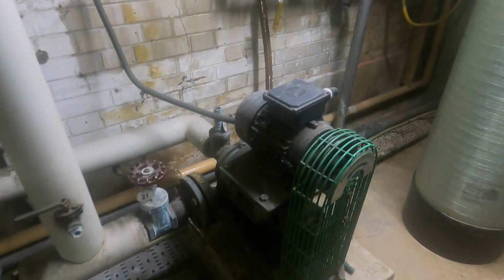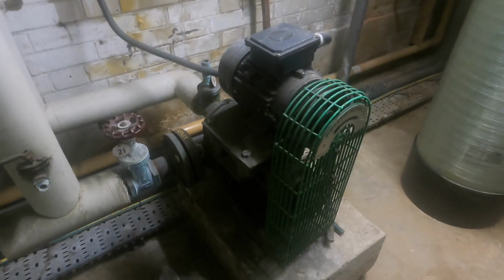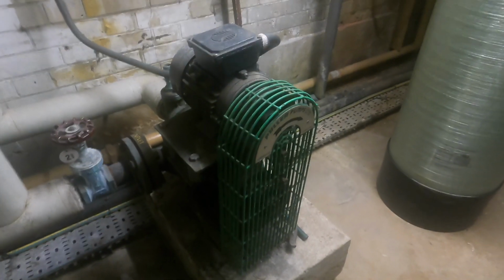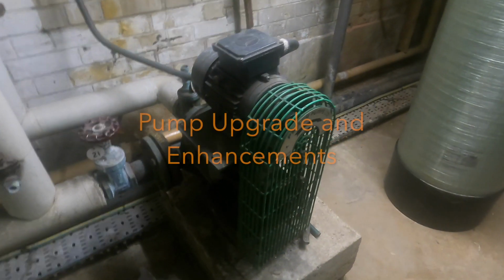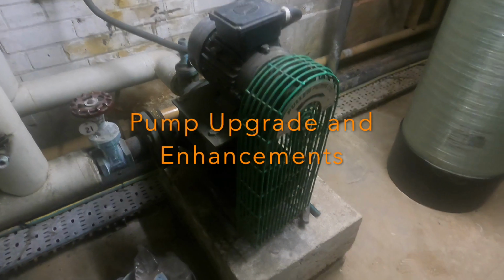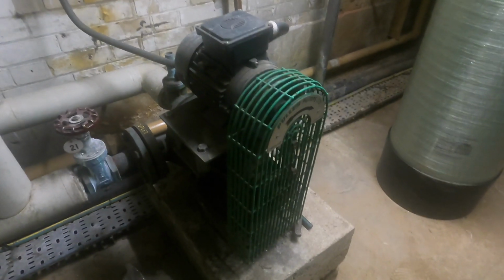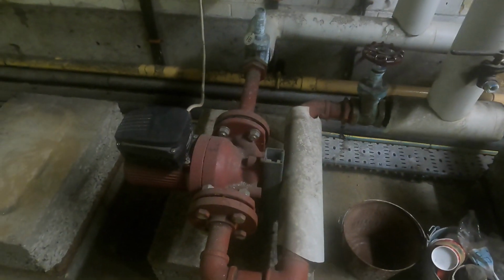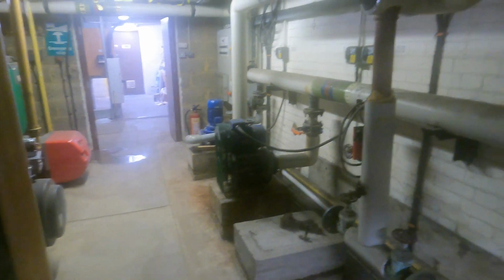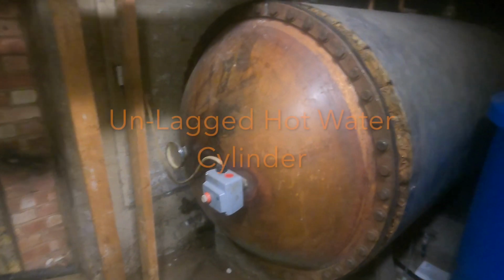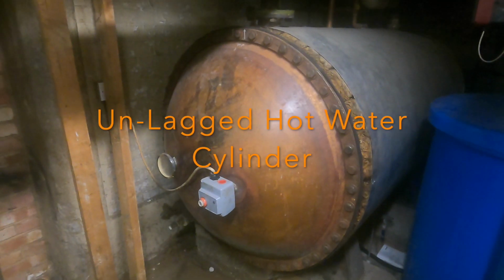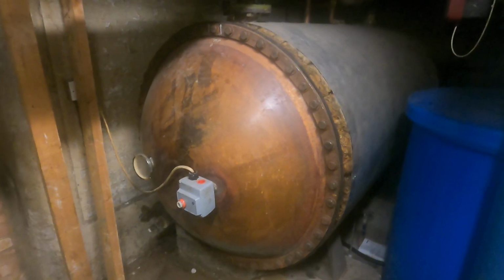I did say that was the last reference point, but there are other points regarding if we were investing in this plant room, we could change these pumps to be more of a direct pump like this one here. So all these pumps could be revised and changed. And then as we're walking out of the plant room, we just had to highlight this area where we've got a very unlagged hot water cylinder.